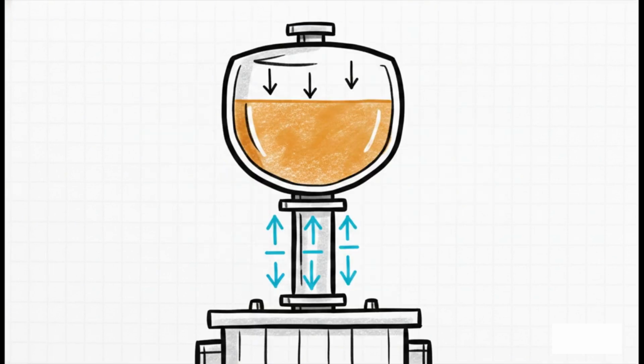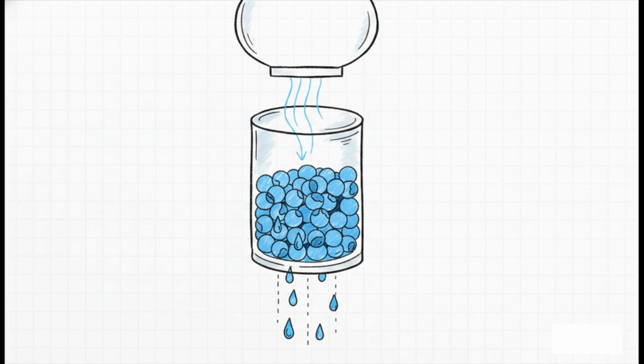The fluid flows smoothly back down through the connecting pipe, retreating from the conservator and returning to the main tank in a continuous, gravity-fed flow. As the hot oil cools and shrinks, the extra volume drains right out of the top chamber. This causes the oil level indicator on the top tank to visibly drop back toward its normal resting position. But here's a totally fascinating engineering detail. As that oil level drops inside the conservator tank, it actually creates a void, a vacuum. To fill this void, atmospheric air is pulled into the tank.